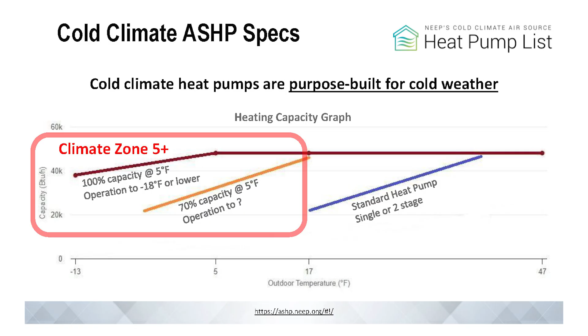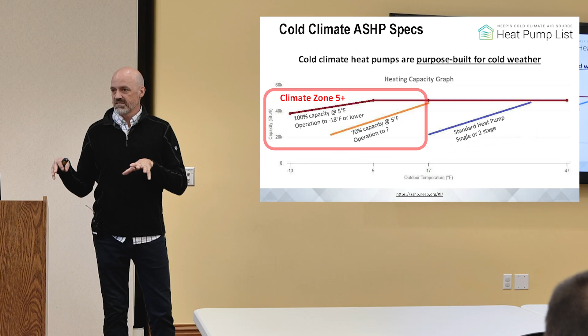That's a small segment of what's listed on NEEP—there's more than 130,000 matchups listed. That's a lot of different systems to pick from. How do you pick the right one? First, ignore the 70%. Second, look at the 100% capacity rating for your location, and how you design to and select that piece of equipment—so Climate Zone 5 plus.